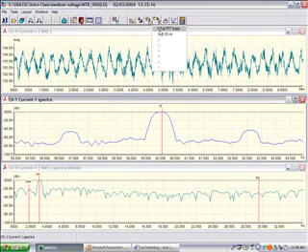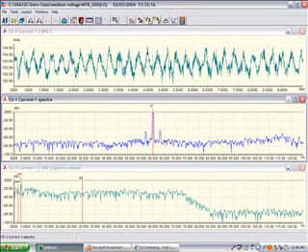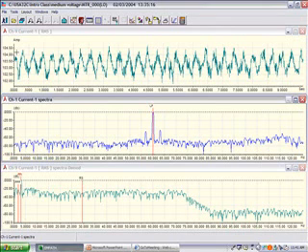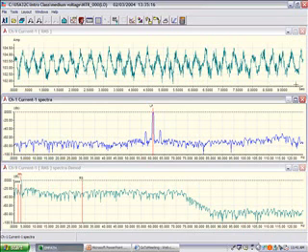If I zoom in here, this top screen is an indicator of current. Now, you'll notice that the current goes up and down from just over, just almost 104 and a half amps down to about 102 amps. Mind you, this data was taken through a CT on a compressor motor. You'll notice that this is happening at regular intervals across a 10-second time period.